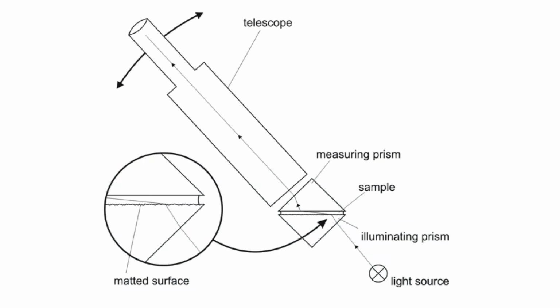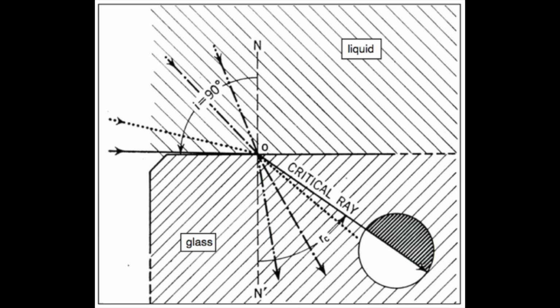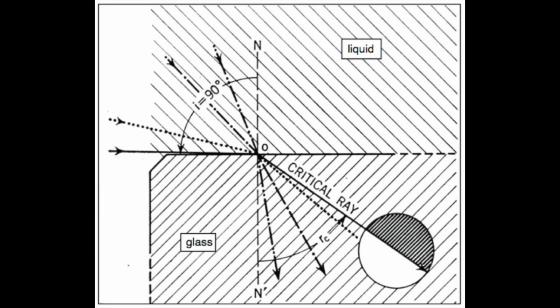In a refractometer, a thin film of the liquid to be tested is spread onto the surface of a measuring prism and a roughened translucent cover or illuminating prism placed over it. This allows light to enter the liquid prism interface at multiple angles. Past a certain angle of incidence, known as the critical angle, light would have to refract past an angle of 90 degrees. As this is impossible, it is instead bounced away via total internal reflection, the same phenomenon behind fiber optics. Below this angle, light is transmitted through the prism onto a reticle.